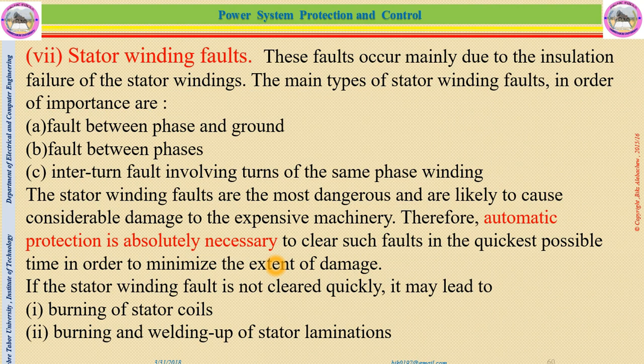The other fault of the generator, the seventh one, is stator winding fault. Those faults occur mainly due to the insulation failure of the stator winding. The main types of stator winding faults, in order of importance, are fault between phase and ground, fault between phases, and inter-turn faults involving turns of the same phase winding. Now let us see those three types of faults in stator winding. Stator winding faults are the most dangerous, and they are likely to cause considerable damage to expensive machinery. This is because the stator winding in most generators is found on the external part of the generator, going to the substation or the bus bars. So this is very critical for generator faults.